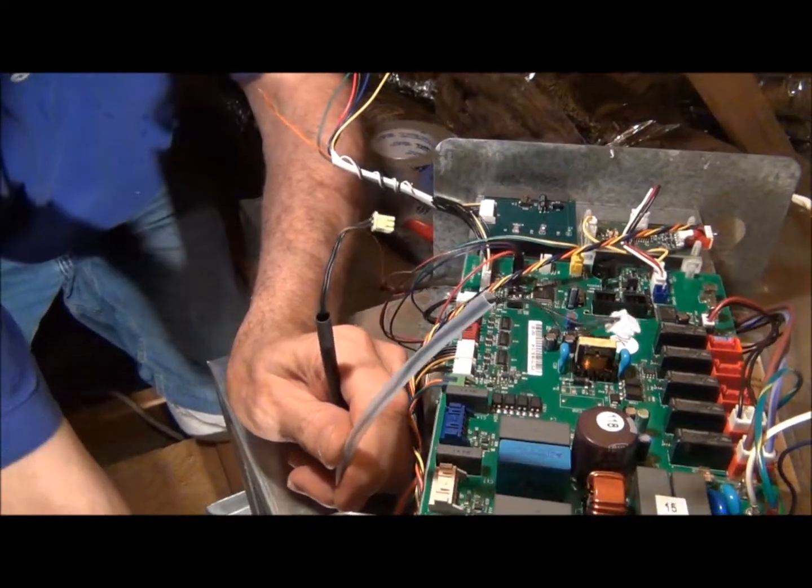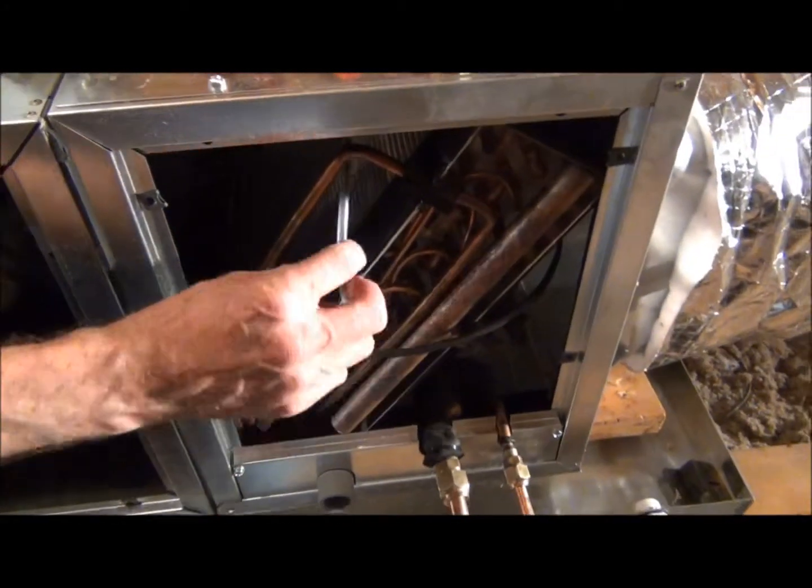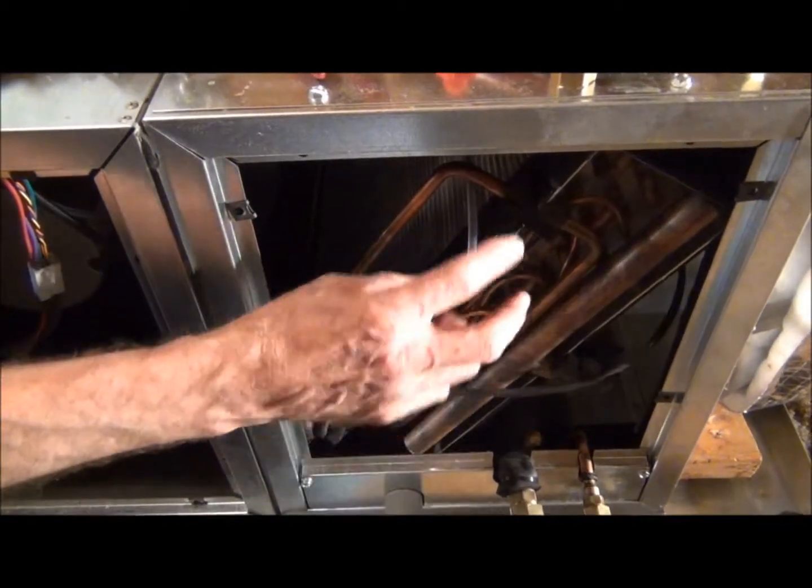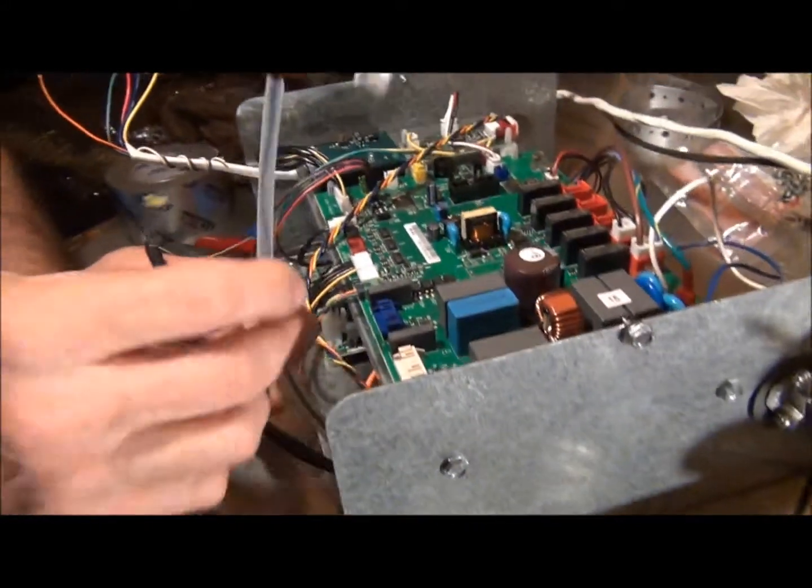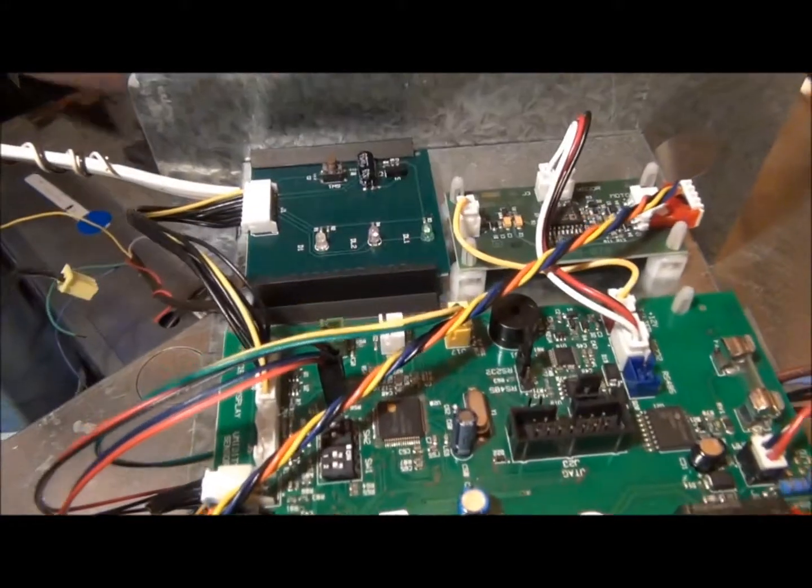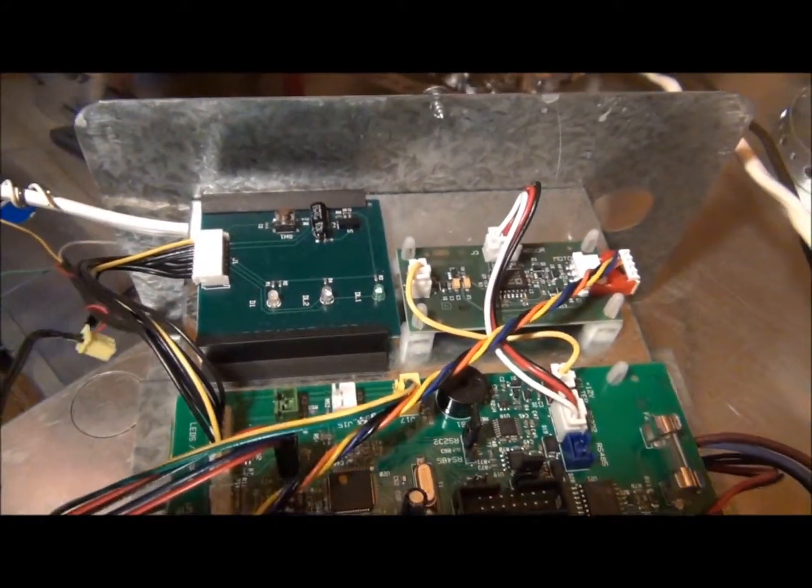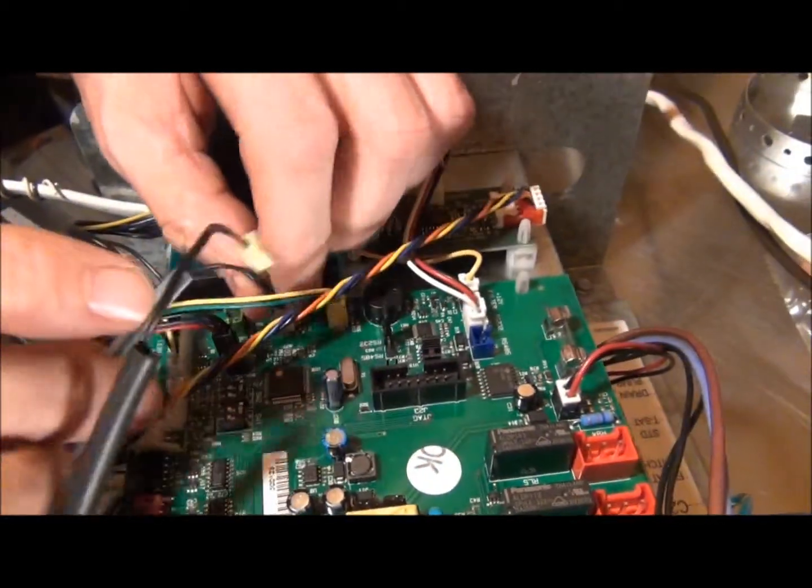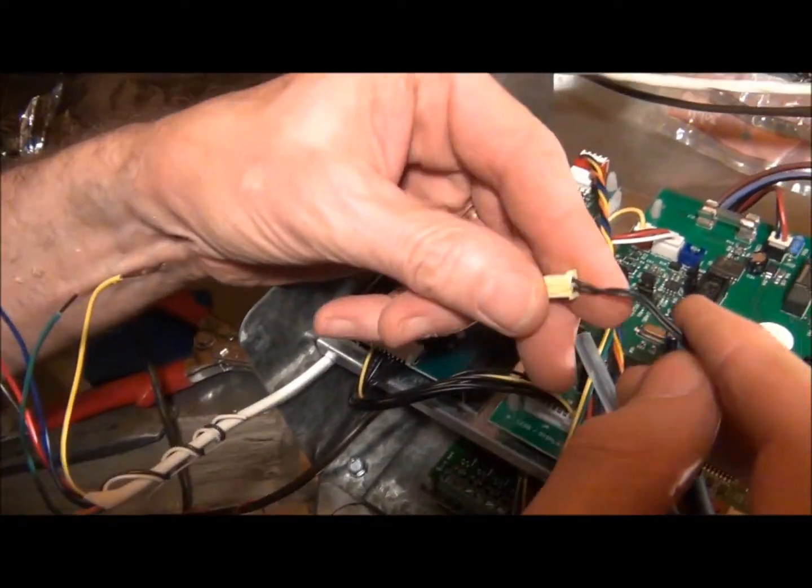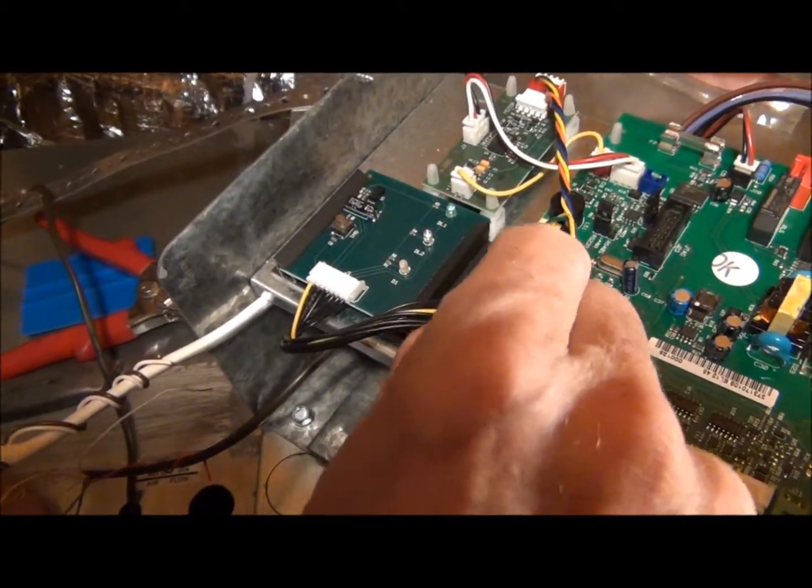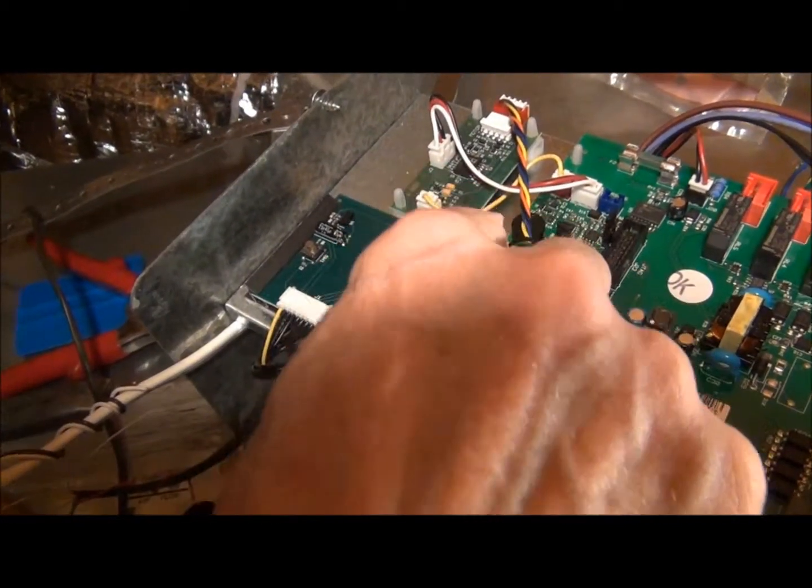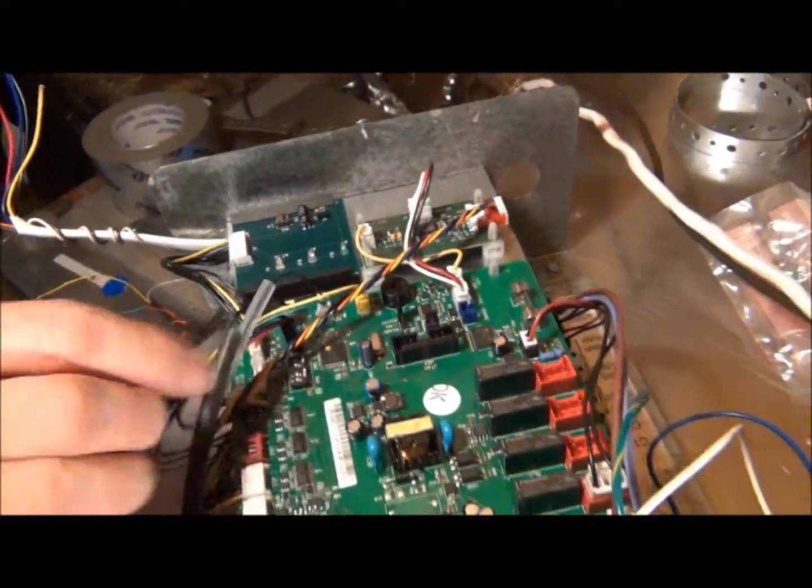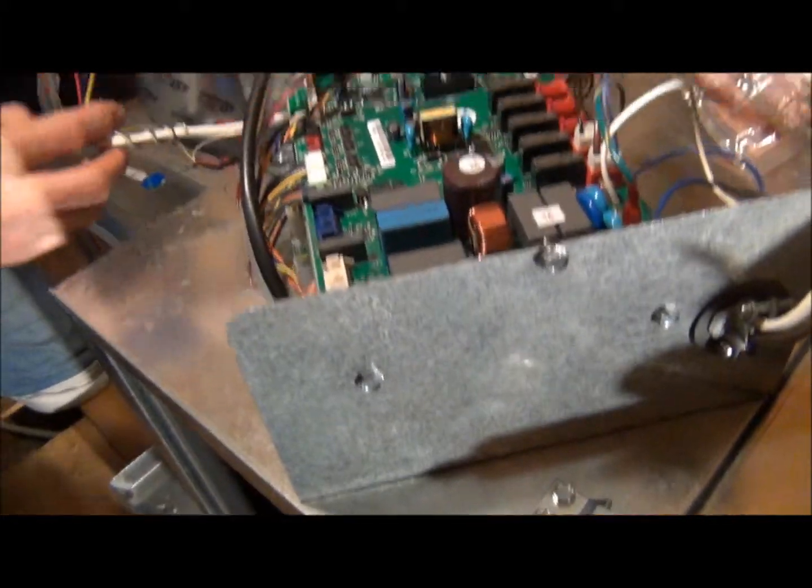Inside the coil there are two sensors: one air sensor and one coil sensor. The coil sensor is the clear one and plugs into where it says coil sensor CT1. This is light green which matches the return air temperature (RAT), and that plugs in. This has to be done in the field.